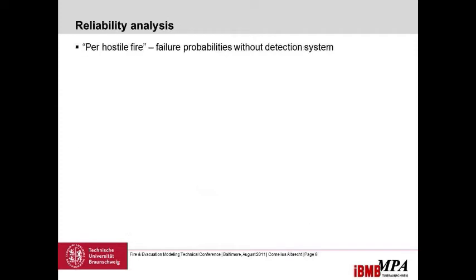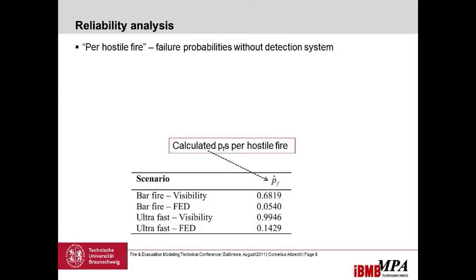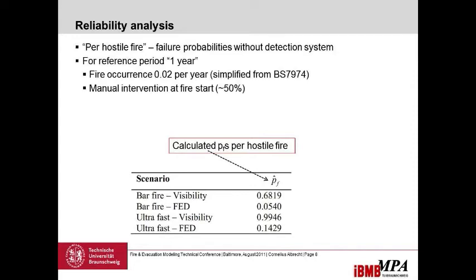I calculated per-hostile-fire probabilities — meaning you assume a fire has already started. These probabilities are actually really high: for the bar fire, it's about 70% failure, meaning visibility of around 10 meters is underrun before the last person has left. For the FED value, it's around 5% for the bar fire, and for the ultra-fast scenario, visibility is underrun nearly all the time. For incapacitation it's about 15%. But these are per-hostile-fire, and we need a fire probability of occurrence of approximately 2% per year — a simplified assumption from the British Standard.